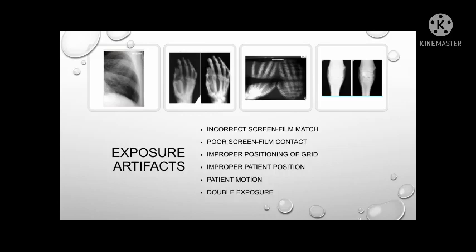Another exposure artifact is the improper positioning of the grid, which results in a uniform reduction of density across the entire film. Improper patient position and patient motion are also exposure artifacts that may cause blurring on the radiograph. A clear instruction and proper immobilization technique should be applied if needed. Double exposure is also an exposure artifact, where two exposures are made on one radiographic film prior to processing. This is common on mobile radiography due to mixing up of exposed and unexposed cassettes. Proper labeling of the holders should be applied to avoid this.